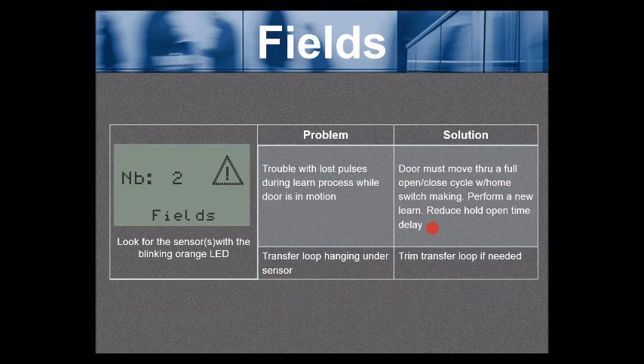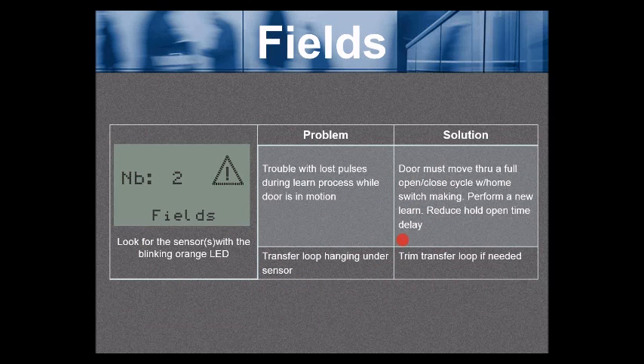So if you have an extended hold time on your door control, you want to turn that down. You don't want the door to stay open too long and then the system will just time out and you'll see a fields error.